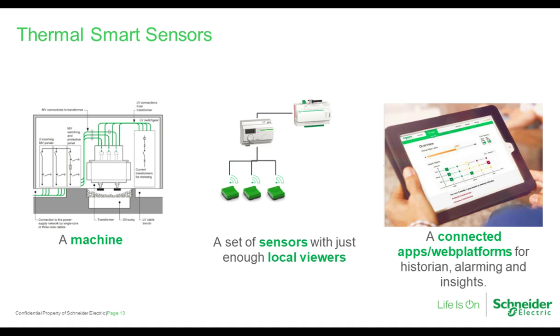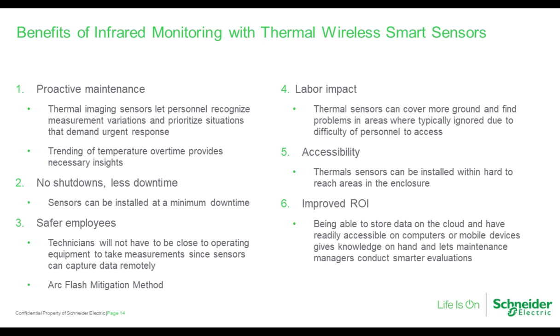Some of the benefits of infrared monitoring with thermal wireless sensors in lieu of thermographic IR window ports is that it's more proactive maintenance. Thermal imaging sensors can let personnel recognize measurement variation and prioritize situations that demand urgent responses. With online thermal sensors, you can see those heat variations at all times. You can also compare it to what's happening in your system, if there's a load increase or if the outside temperature is increasing. Thermographics using IR windows is only a temporary shot of what's happening in that system while you're taking those pictures, and it's not always as valuable as continuous online monitoring.